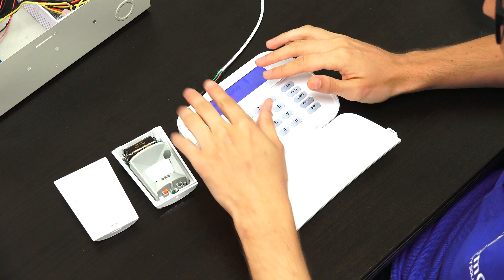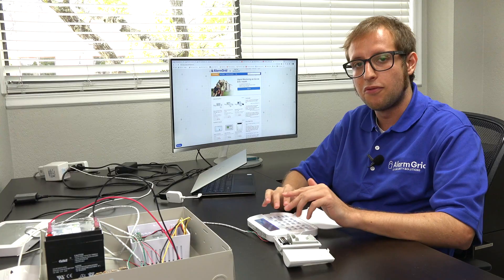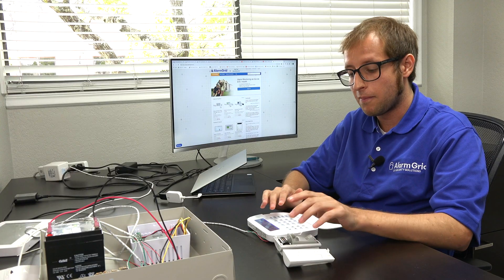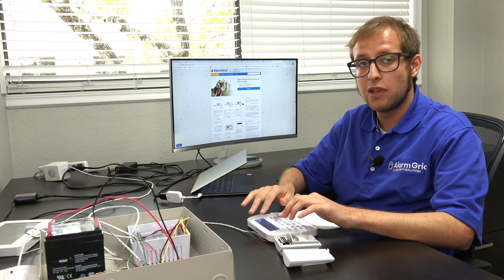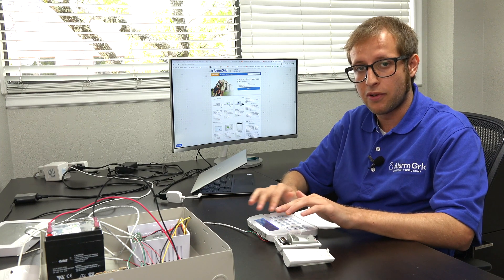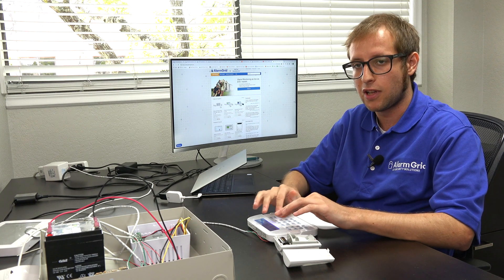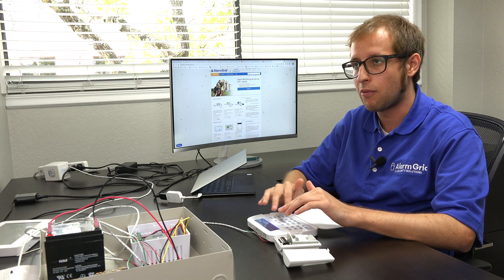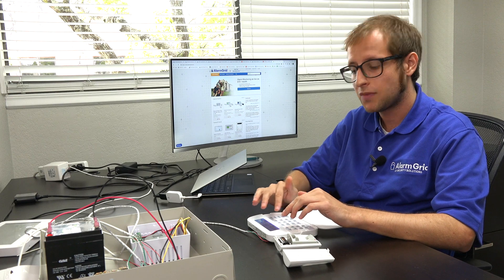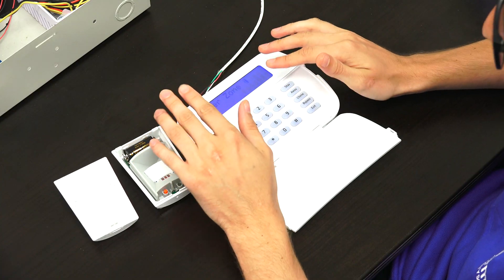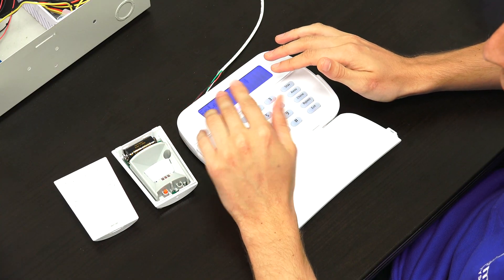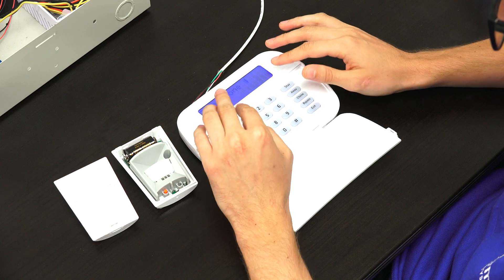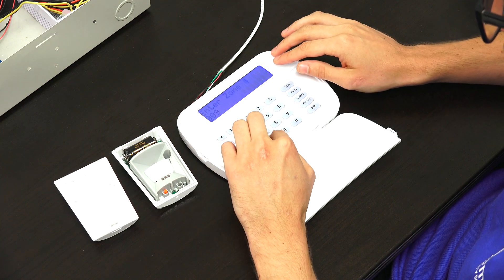So we're just going to press star to continue. And now it wants us to choose a wireless zone for the sensor to enroll to. It's going to give you the first zone available automatically, but you can enter in a different one if you want to. In our case, we're fine with 009. Remember that zones are expressed in three digits on the NEO. So we're fine with that. We'll just go star.